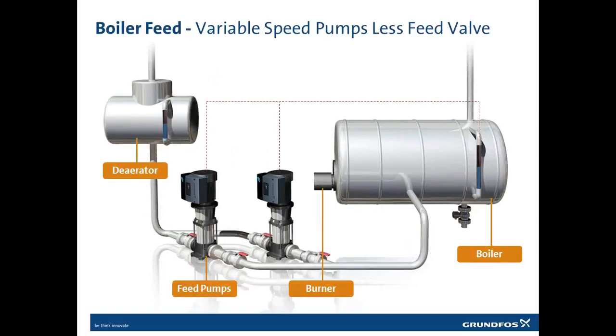Running on volts and from 0 to 20 milliamp, you could call it unstable, but it's not. It can be influenced by disturbances on the grid and harmonic distortions and other stuff. So they are not as stable or as good to use as the 4 to 20 milliamp signal.